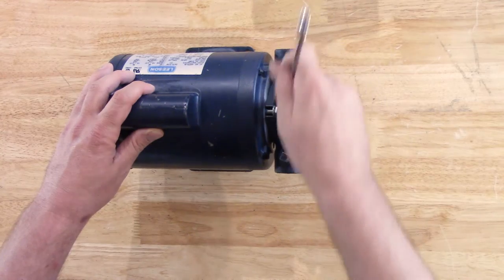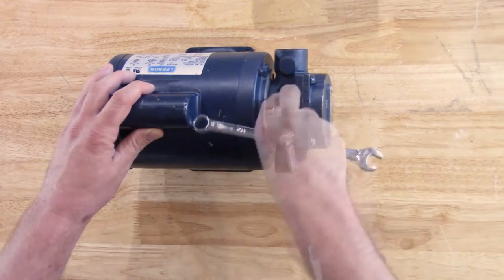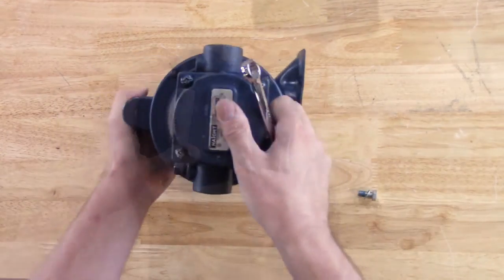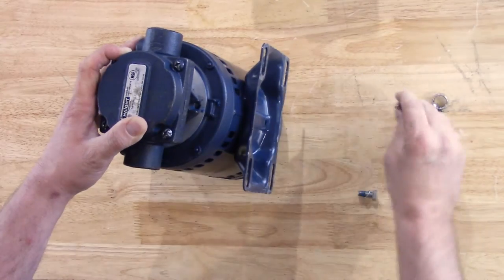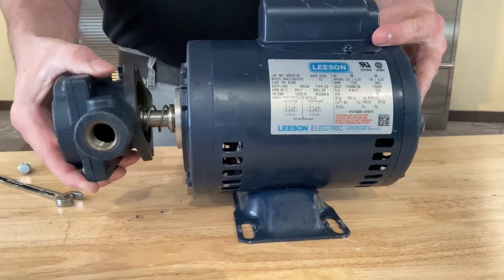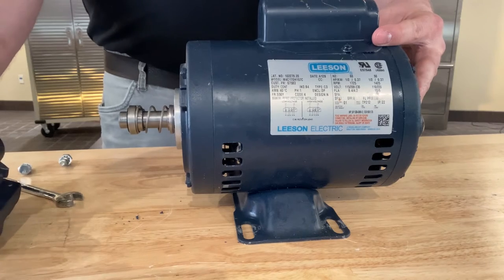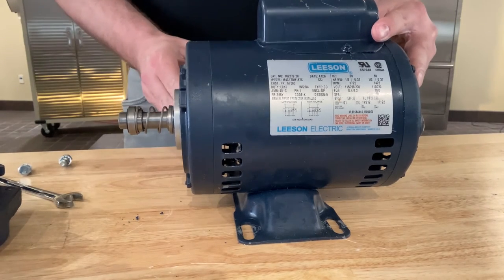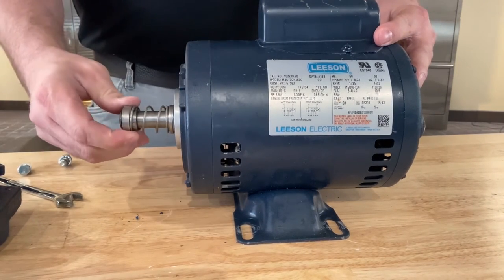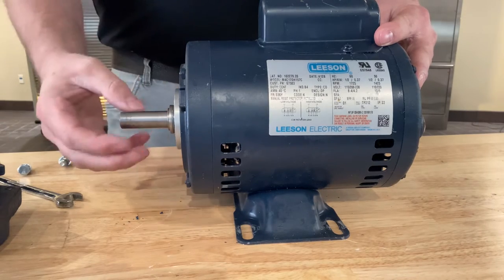To replace the seal kit, start by removing the two flange bolts that mount the pump to the motor. Now that the two bolts are removed, we can remove the pump body from the motor and expose our seal components. Once we have them separated, we can remove these seal components and set them to the side.